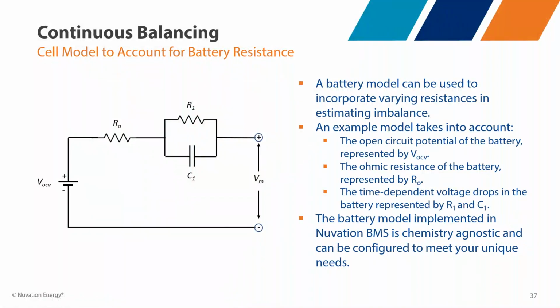Let's talk about what we call continuous balancing. Inside the BMS we have a model of the individual cell. There's the open circuit voltage of the cell, the actual voltage across the internal cell. The voltage we measure is out here, but it has other components: the ohmic resistance of the battery, represented by R0, and a time-dependent voltage drop represented by R1 and C1. All of these individual elements are modeled inside the BMS so that we can calculate the actual open circuit voltage.